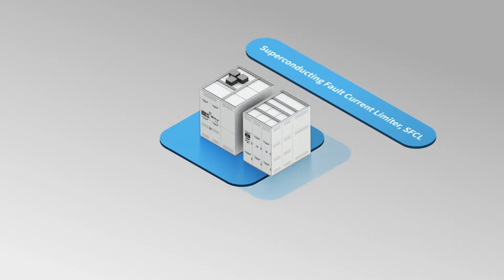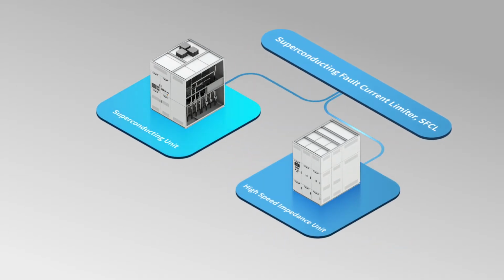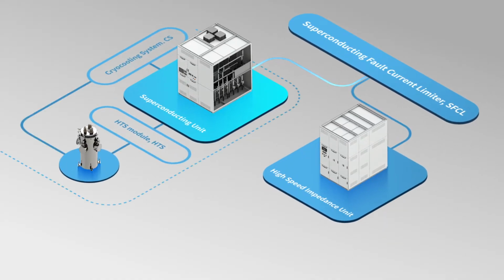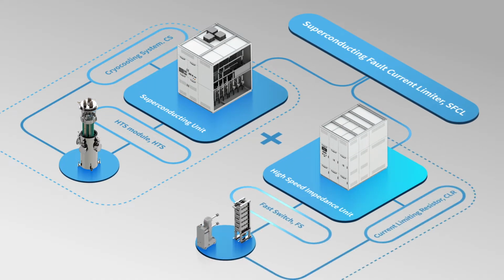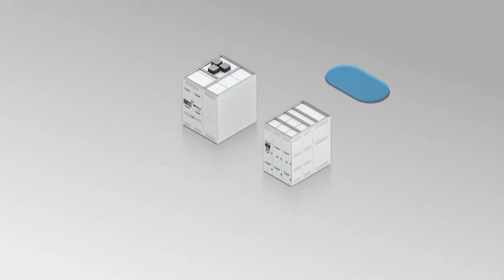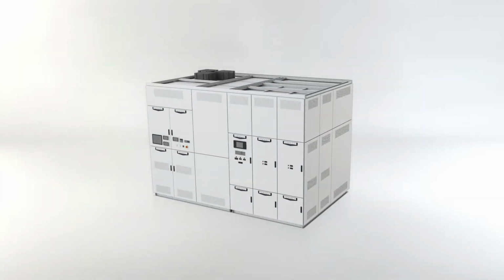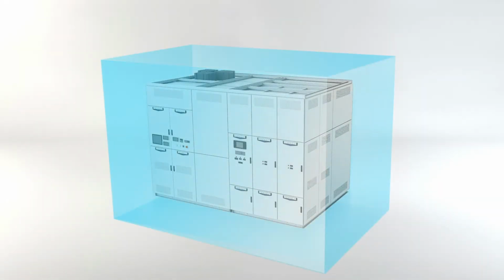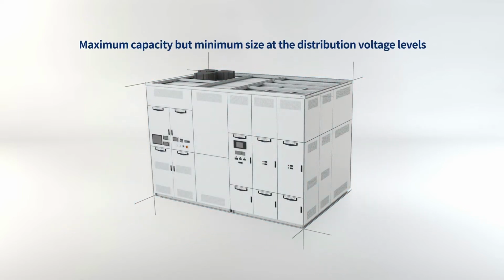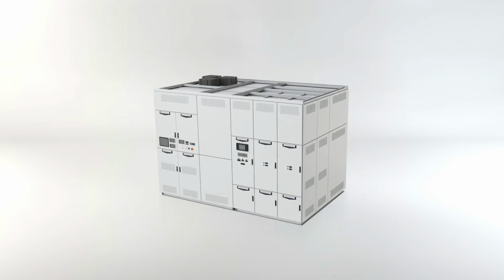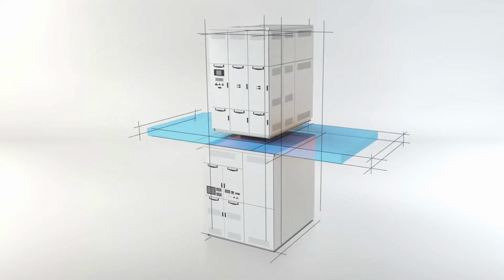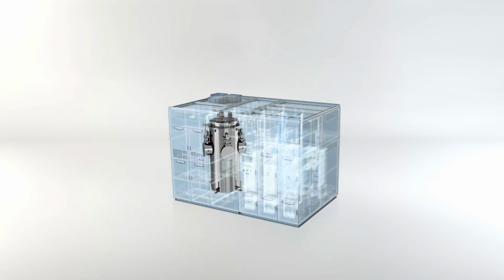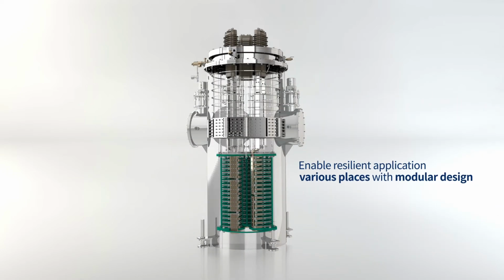SFCL is composed of a superconducting unit in charge of current limitation at the half cycle of the fault current, the first peak of the fault current, and the high speed impedance unit in charge of fault current limitation after the half cycle. With its composition, LS Electric has successfully developed SFCL, the smallest size, but boasting maximum capacity at the distribution voltage levels. Especially, LS Electric's SFCL is easy to install without any spatial restrictions. And its modular design enables resilient applications in various places.